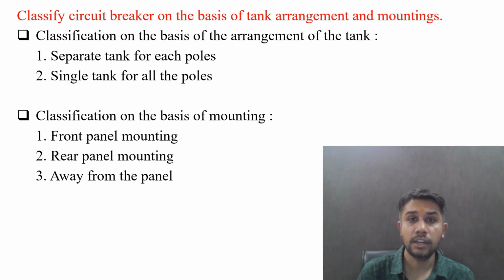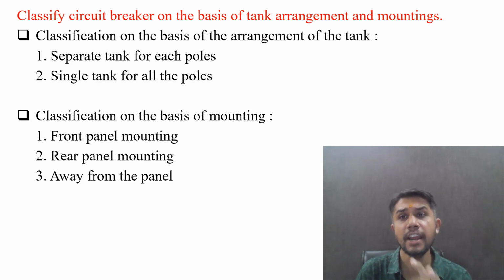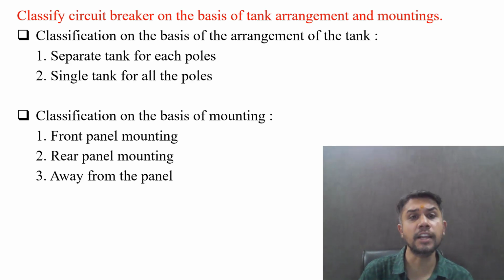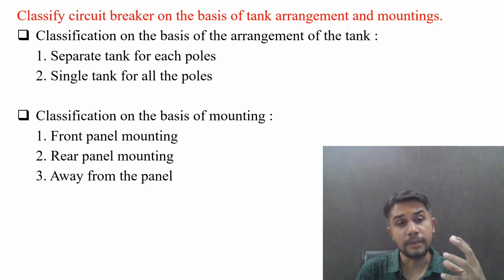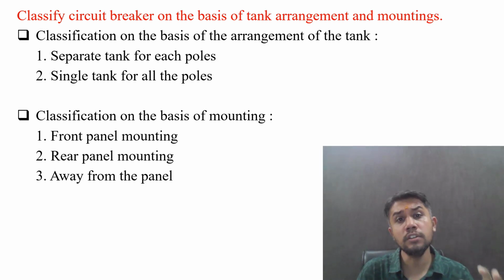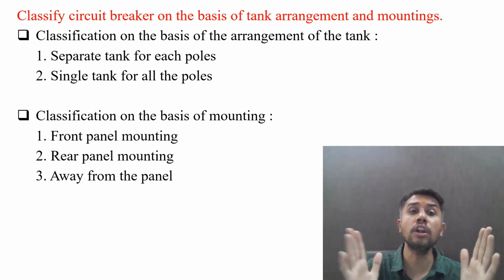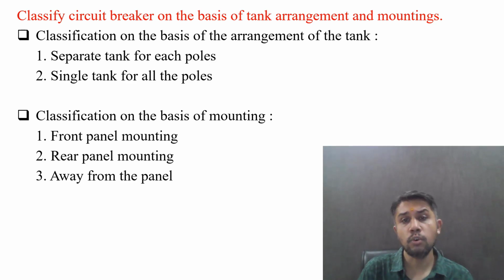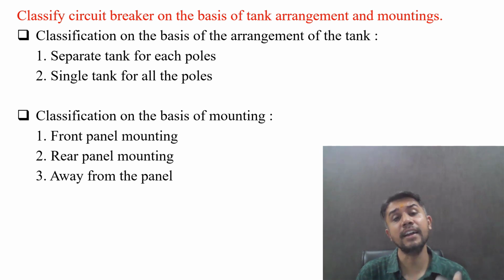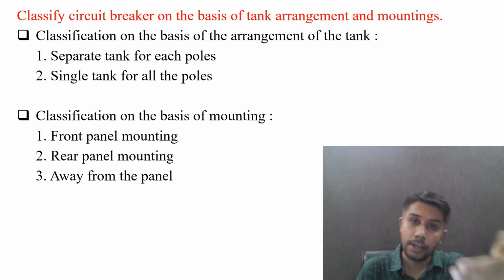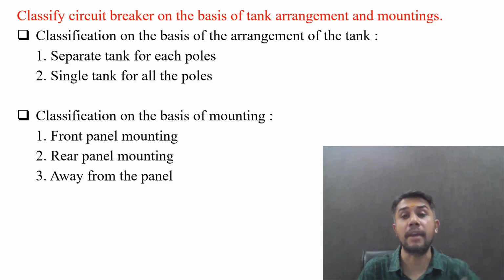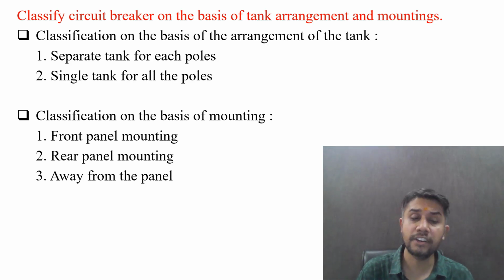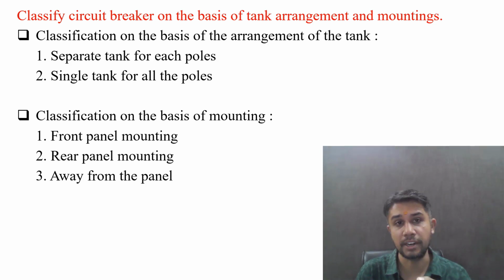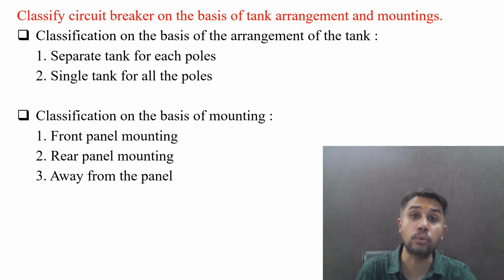Classify circuit breaker on the basis of tank arrangement and mountings. So on the basis of arrangement of the tank, the circuit breaker can be classified into 2 types, that is separate tank for each pole and single tank for all poles of the circuit breaker. Now on the basis of mounting, they can be classified as front panel mounting, rear panel mounting or away from the panel. So there are three different types of mounting arrangement for the circuit breaker. So this is how the circuit breaker can be classified on the basis of tank arrangement and mountings.